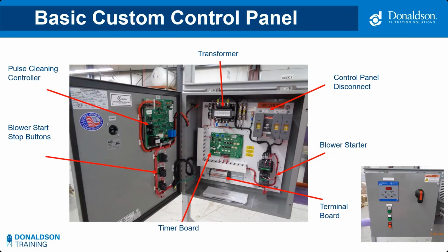Moving over to the inside view of the panel, the arrow pointing to the control panel disconnect happens to be pointed at the line side of that fusible disconnect. Please note that the line side voltage of that disconnect will remain live unless the power is also turned off further upstream. The wires you see going down and out of that disconnect are the load side. When the disconnect is in the off position, the load side is disconnected, but the line side could in fact remain live.